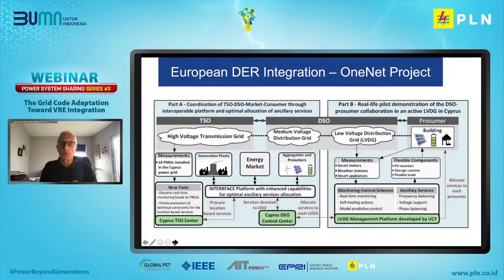This is happening in Europe as well. There are many projects looking at coordination between the TSO and the DSO, aggregators, and distributed providers to make sure we can accomplish this integration. It relates to grid codes because grid codes must support the constraints and requirements of the local distribution system, as well as making sure they support frequency stability, voltage stability, and resiliency of the overall transmission grid. Getting that balance is very important.